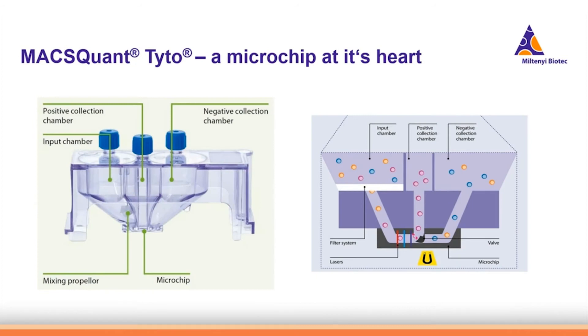At the heart of the MACSQuant Tyto there is a microchip. The cells are inserted into the input chamber. At the bottom there is a mixing propeller keeping the cells in suspension at all times. Cells are sorted into the positive collection chamber and the non-target cells will all flow through to the negative collection chamber. At the bottom of the cartridge there is a microchip.